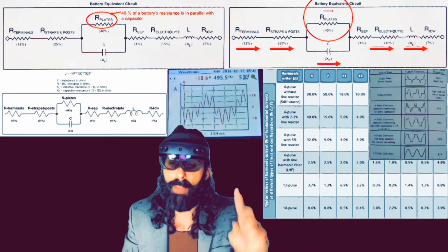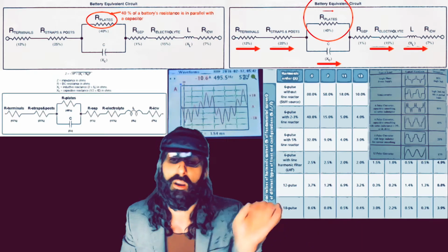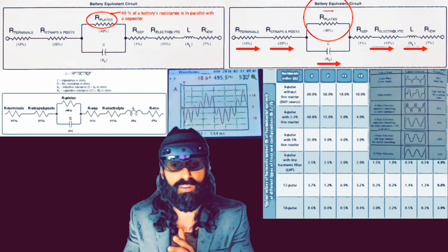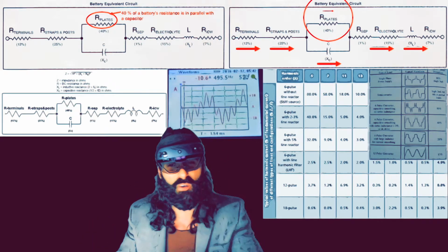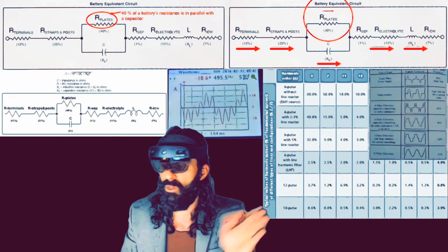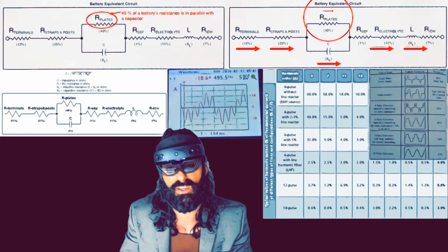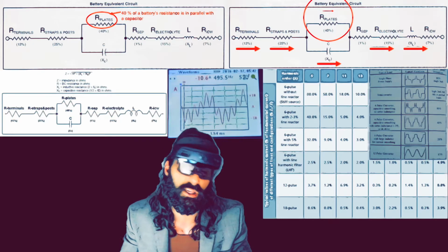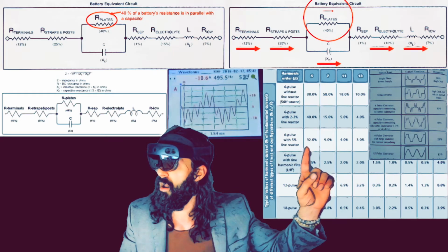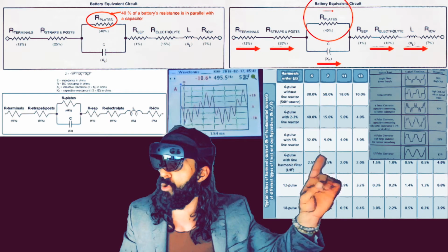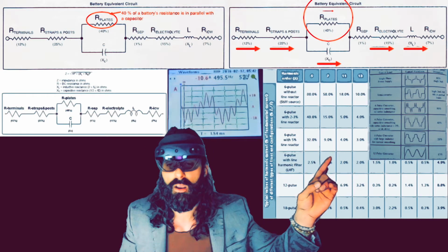You'll see on this side, depending on if you have a 6-pulse rectifier or a 12-pulse rectifier, or if it's an SCR or IGBT, we know IGBTs can turn off and on instantly, but SCRs actually take some time. We'll go over that a little bit later, but because of that, you get more noise with SCRs on DC buses than IGBTs, and specifically IGBTs have different generations. They can switch at different kHz, 14 kHz to 60 kHz. So you'll see different representations all the way on the other side of how that signal level and the typical waveform that you see in a 3-phase output actually looks on 6-pulse rectifiers or 12-pulse rectifiers.